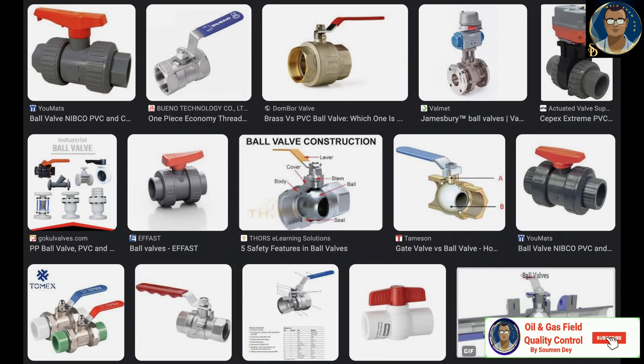Ball valves are equipped with quick-acting 90-degree turning handles. They use a ball to control flow and provide easy on/off control. They are generally considered faster and easier to operate compared to gate valves. Butterfly valves are compact, quick-acting rotary motion valves ideal for tight spaces. Butterfly valve bodies are found in various configurations.